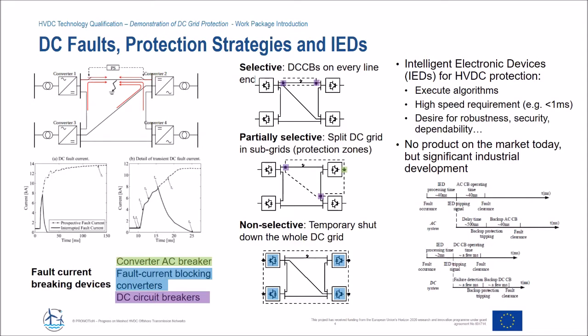And to achieve these, there's a number of different current breaking devices that can be used. You could rely on the converter AC breaker, but this could potentially be a bit too slow for a DC grid. You could use the fault current blocking converters, or indeed DC circuit breakers. Now, underpinning all this are the so-called intelligent electronic devices, or IEDs for short. Now these are devices that have been under test mainly through work package 9, and these execute the protection algorithms and are the things that instruct whatever your fault breaking device is to operate.